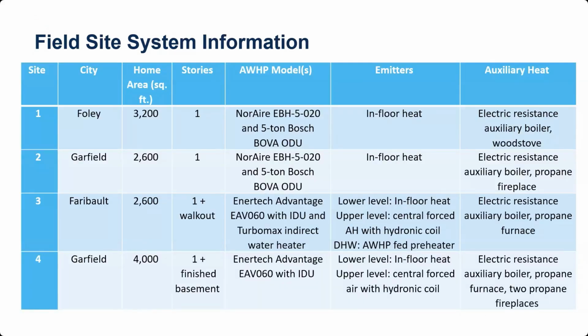So here is a table for details on these sites and systems. Site 1 was in Foley, Site 2 in Garfield, Site 3 in Faribault, and Site 4 was quite close to Site 2, also in Garfield. The 2 split systems were NorAir third-party split units paired with a 5-ton Bosch Bova non-communicating air source heat pump outdoor unit. Site 1 had in-floor heating as its primary emitter, as did Site 2. Both sites had an auxiliary electric resistance boiler included as part of the IDU package from Electro Industries. Site 1 also had a wood stove in the main living area, and likewise Site 2 had a propane fireplace.